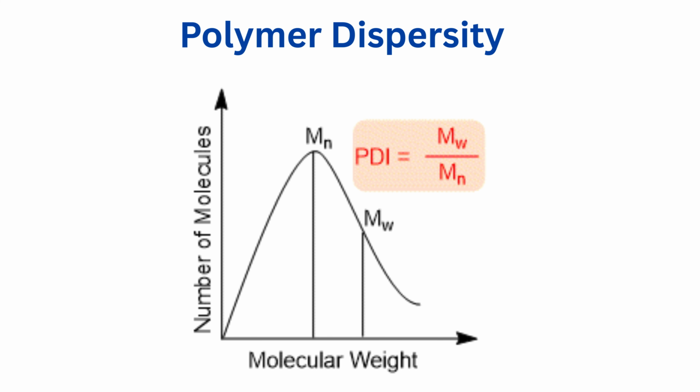Dispersity is basically a representation of the distribution of size populations within a given sample. The numerical value of dispersity ranges from 0.0 for a perfectly uniform sample with respect to the particle size to 1.0 for a highly polydispersed sample with multiple particle size populations. Values of 0.2 and below are most commonly deemed acceptable in practice for polymer-based nanoparticle materials.